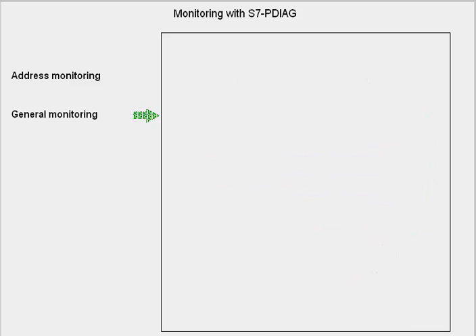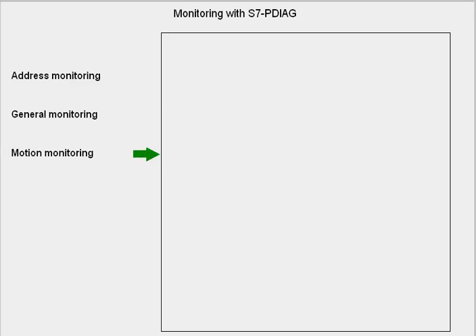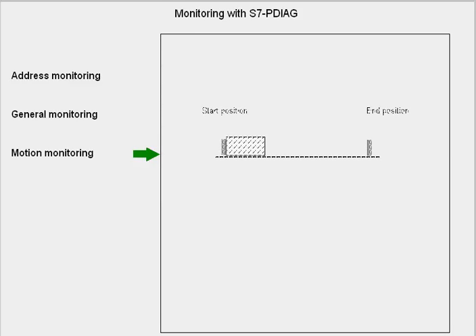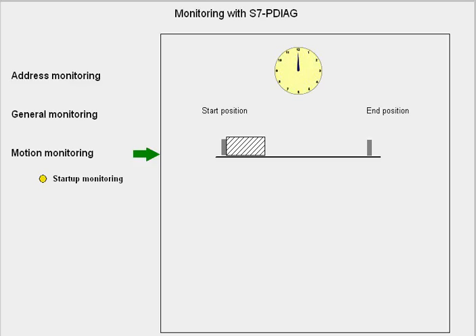For address and general monitoring, you do not need to modify your user program for the monitoring logic. With motion monitoring, you check whether physical movements in your process are being executed correctly and within the specified time. S7-PDIAG offers four different forms of motion monitoring. Start-up monitoring determines whether a movement actually leaves its start position within a predefined start-up time.